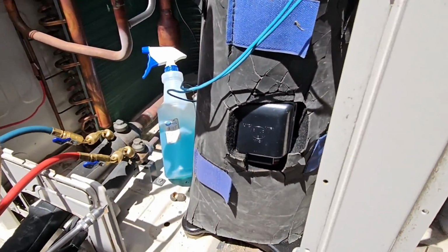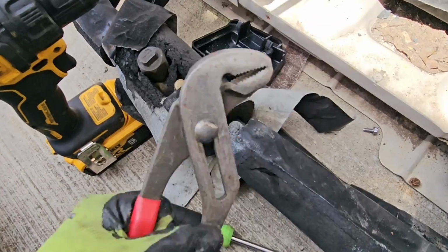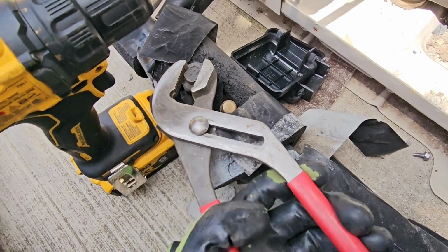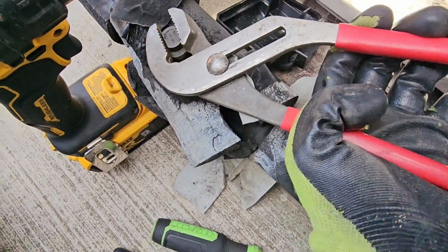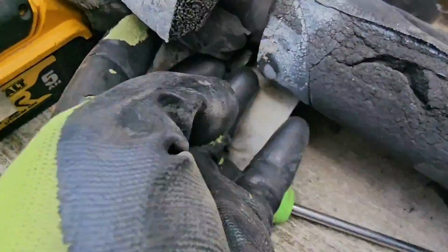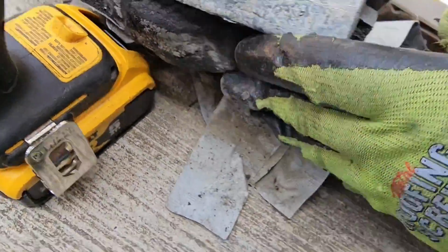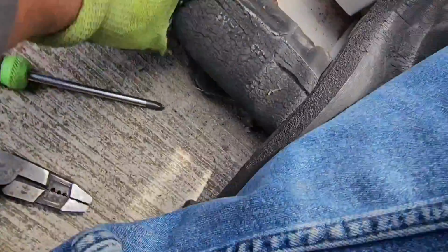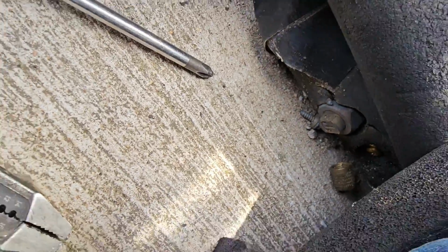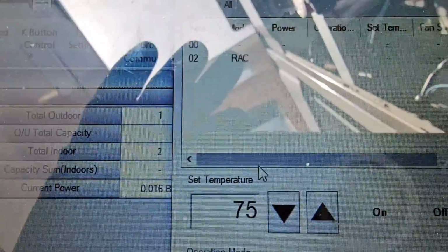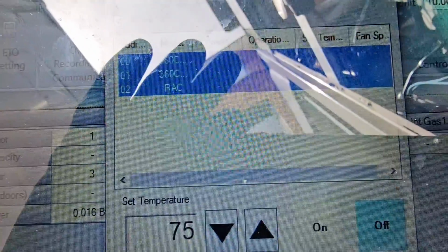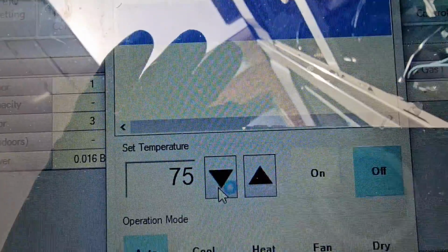Compressor blankets back on. And I need to open up these valves. We've got two of them, that's one. And the other one is, I think it's right there. Yeah, I need to open that one up too. Disconnect back on. Using SNET to go through and select all of the indoor units, 2 360 ceiling cassettes and 1 room air conditioner or wall mount air handler.